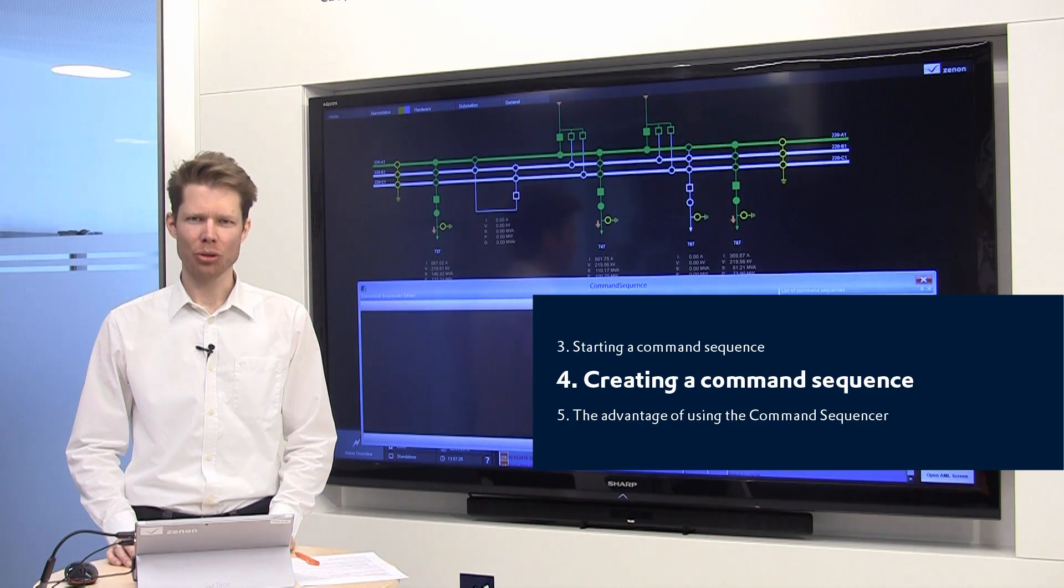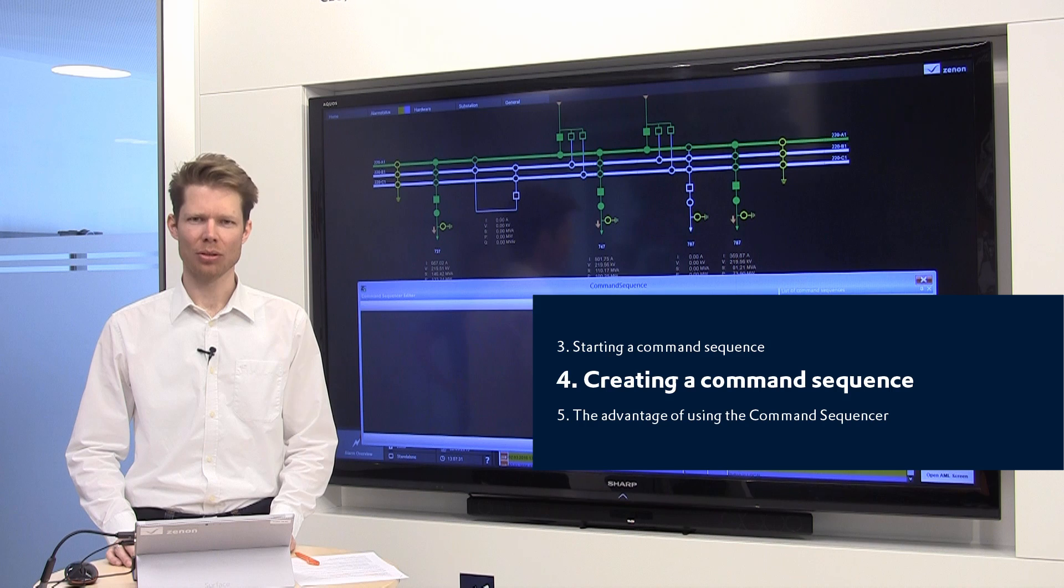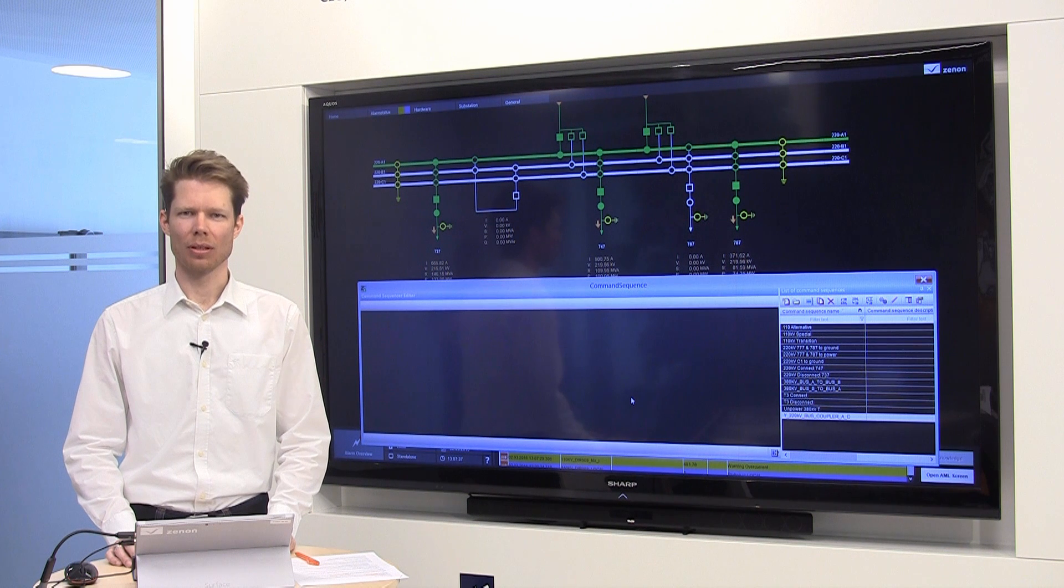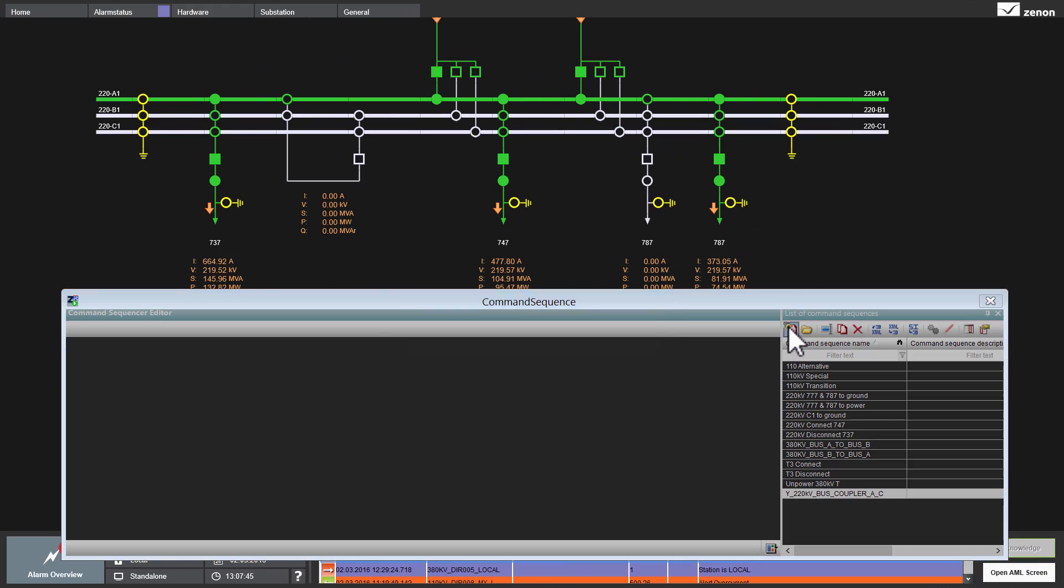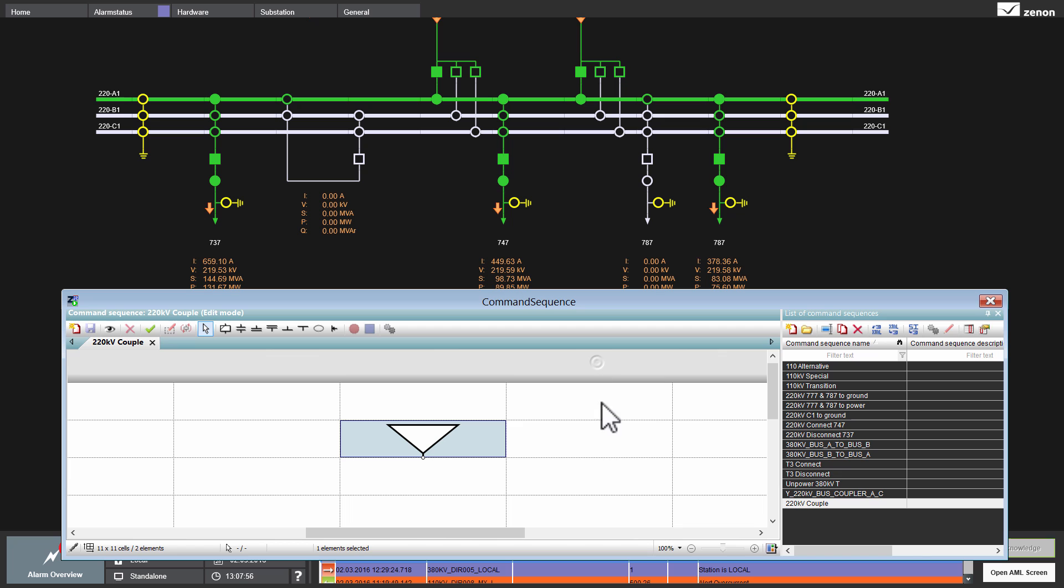Now, I show you how easy and simple it is to create a command sequence. In our 220 kV substation, we want to couple bus A with bus C. For that, I open a new sequence. For instance, I give it the name 220 kV couple and then I enter the steps.